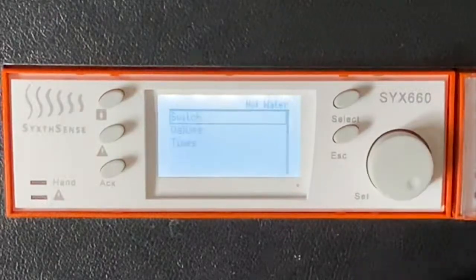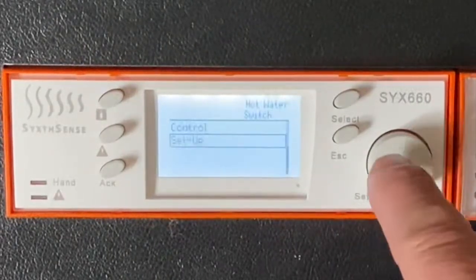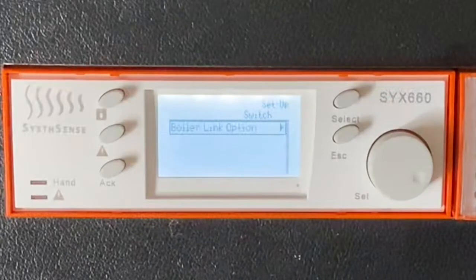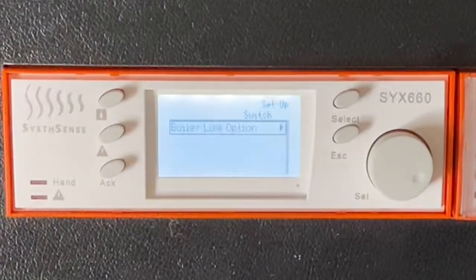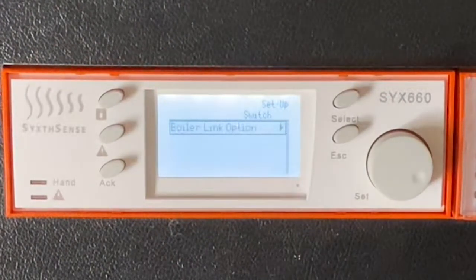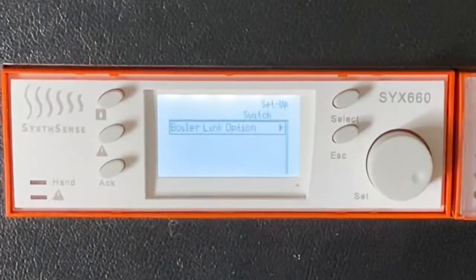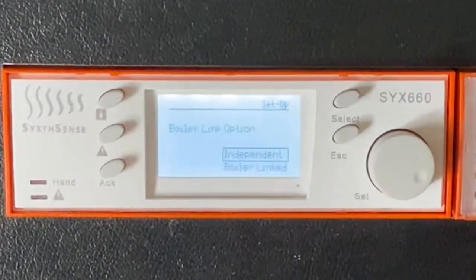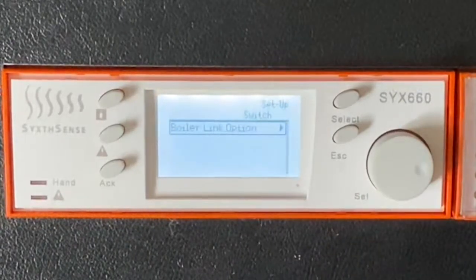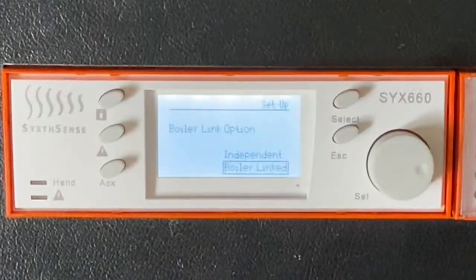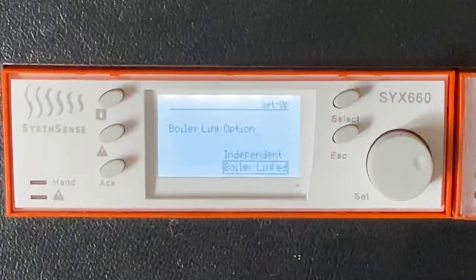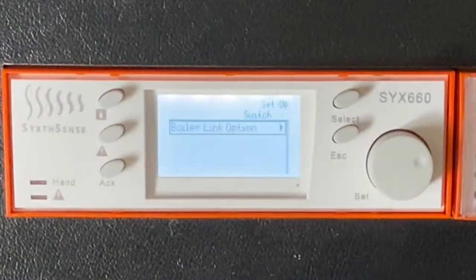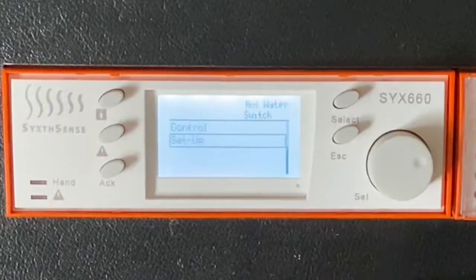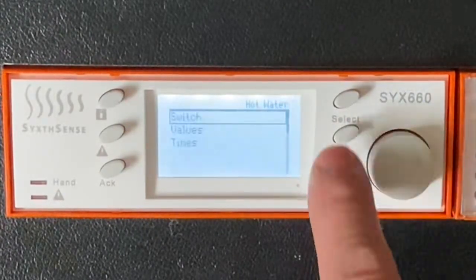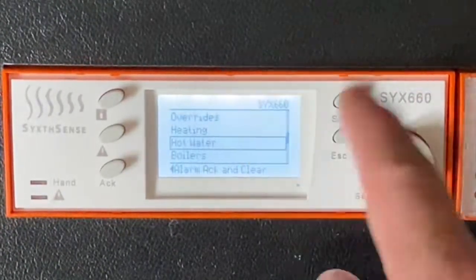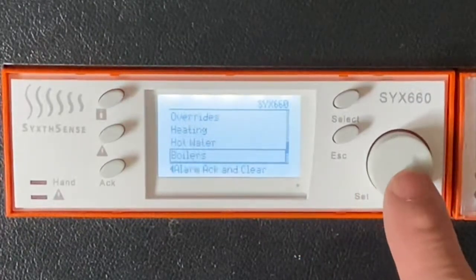So we choose hot water menu, we choose switch, we choose setup, and we have to decide if the hot water is linked to the boilers or it's independent, like a gas-fired water heater. In our case, because we're using the hot water demand system, this system is boiler linked. So I choose link option, turn the wheel, went down to boiler linked, and press set on boiler linked, and that's the function set. I'll just press escape, press escape, press escape, and now I'm back to the main menu again, and now I can set up the boilers.